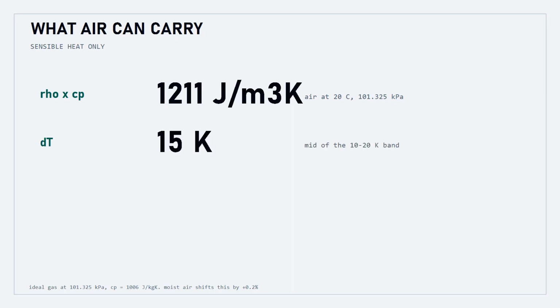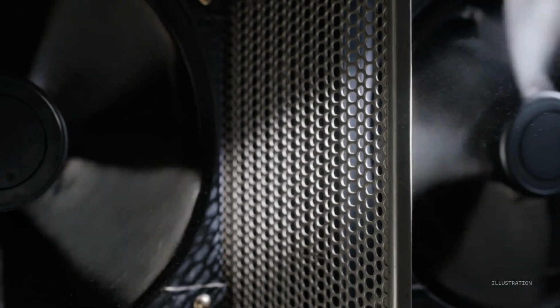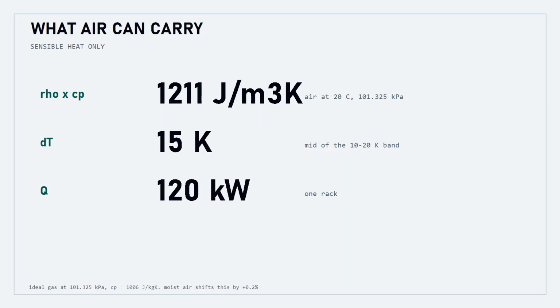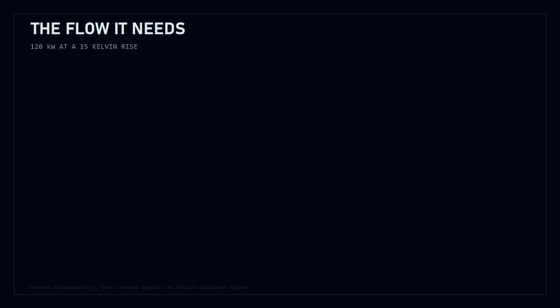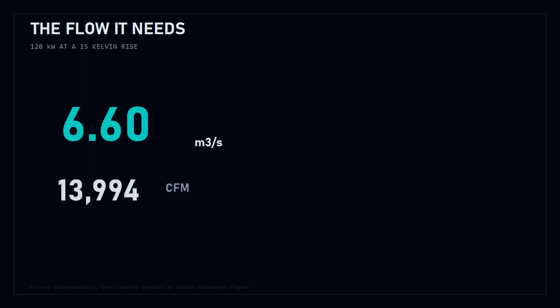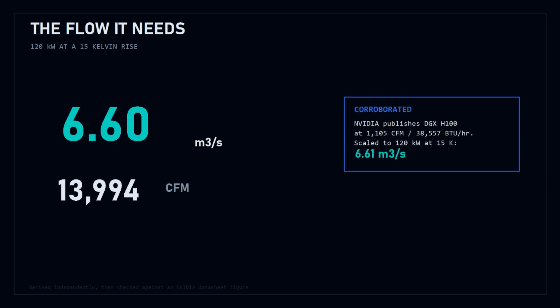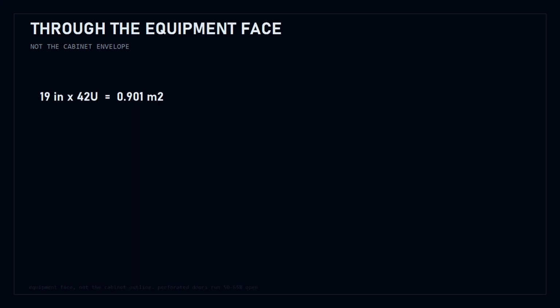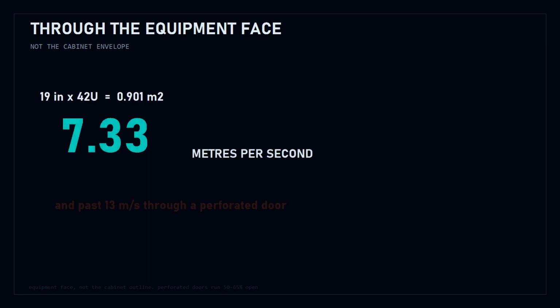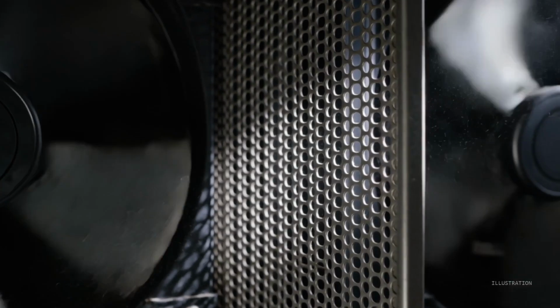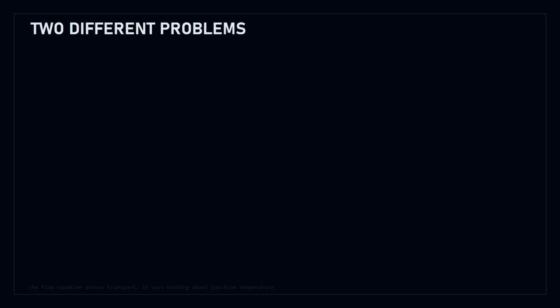Start with what air can carry. At 20 degrees, it holds about 1200 joules per cubic meter per Kelvin. Allow a 15 Kelvin rise across the rack, the middle of the 10 to 20 band real machines run. 120 kilowatts needs 6.6 cubic meters a second, just under 14,000 cubic feet per minute. Across the equipment face, 9/10 of a square meter, that is 7.3 meters a second, and past 13 through a perforated door. So the stream can carry it. That much is arithmetic.